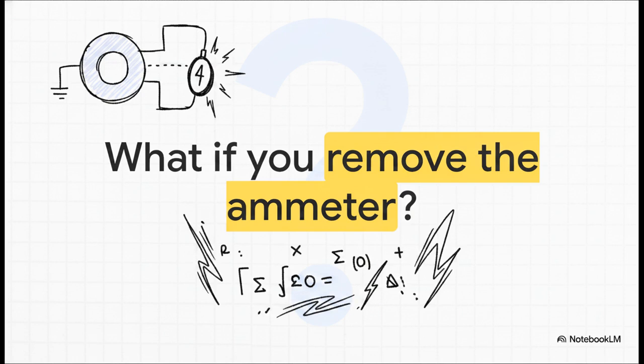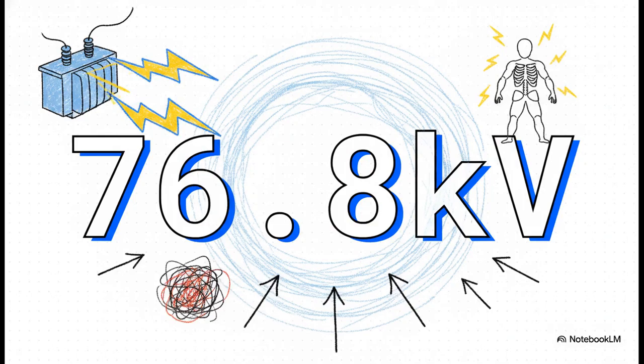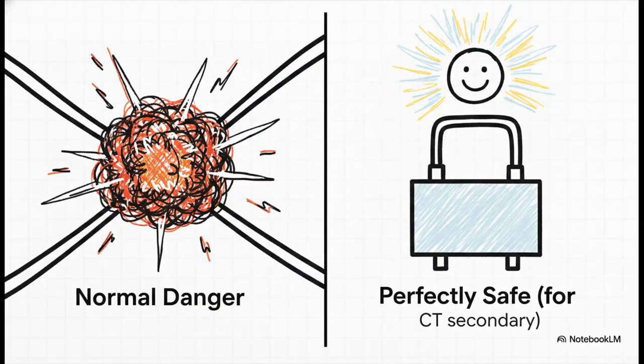But disconnecting the measuring device from an energized current transformer unleashes a massive mathematical and physical nightmare. Because the transformer's coils act in reverse, due to what we call an inverse turns ratio, an open-circuited secondary suddenly turns this safety device into a massive step-up transformer. We're talking instant, lethal induced voltages. Imagine a spike hitting 76.8 kilovolts just because you unplugged a simple meter. The core magnetically saturates, and with no opposing secondary current to keep things balanced, boom, the voltage skyrockets to deadly levels. So how do engineers solve this deadly little trap and stop equipment from exploding?